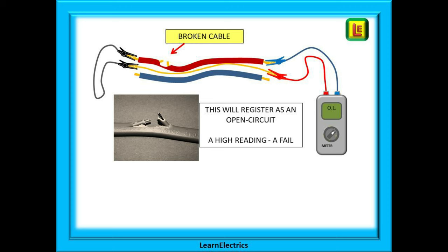What results would we get if one of the cables under test was broken? The path on the phase wire for the returning test current is interrupted — something has caused major damage to the cable. This will register as an open circuit and the meter will indicate a maximum reading: 1999 on my meter, or OL. Because we set our meter correctly we already know what the meter would indicate for a broken circuit. We can record this as a fail, investigate it, and repair.